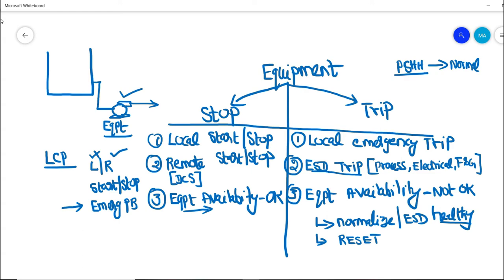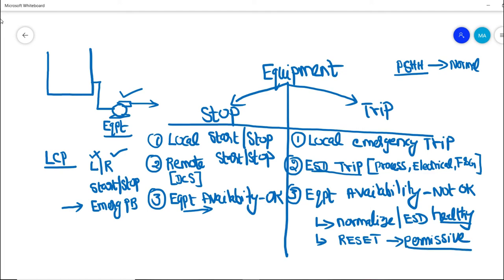The second thing we have to do is reset the ESD trip. What is basically a reset? The area operator or control room operator is acknowledging that all process conditions and safety conditions are okay in the field, so this particular equipment can be started — it can be retrieved from the trip condition.